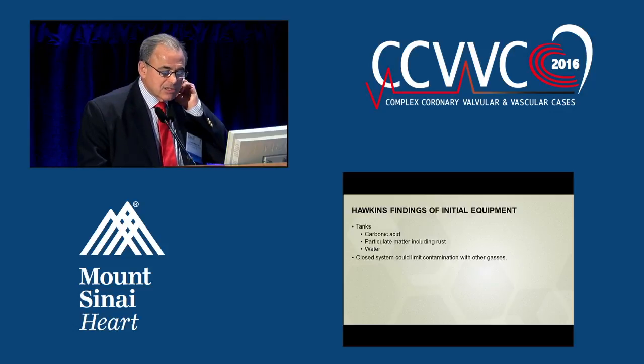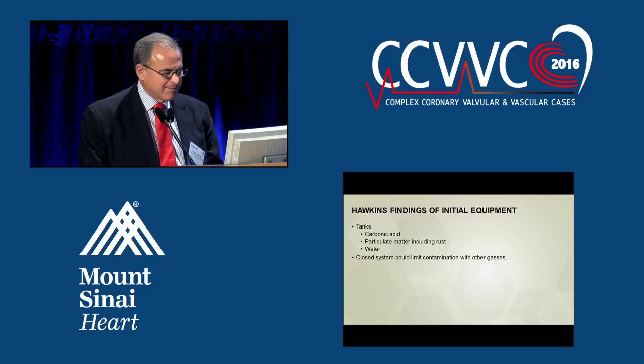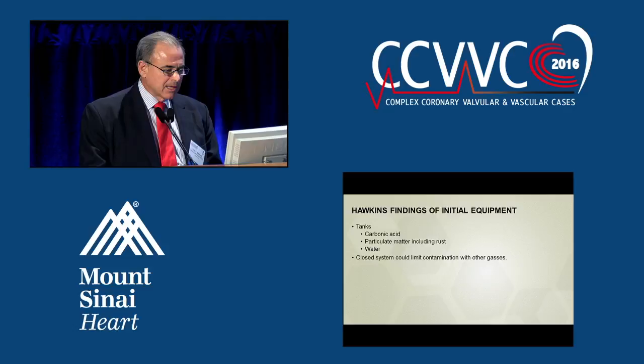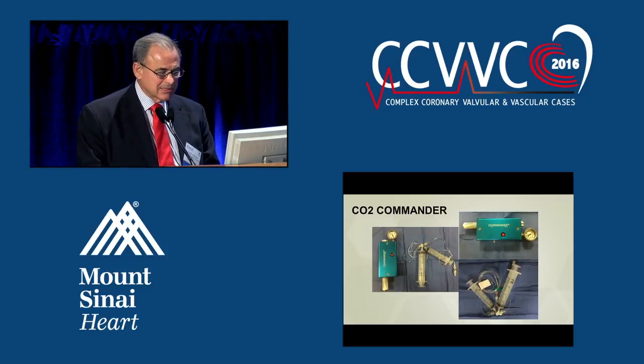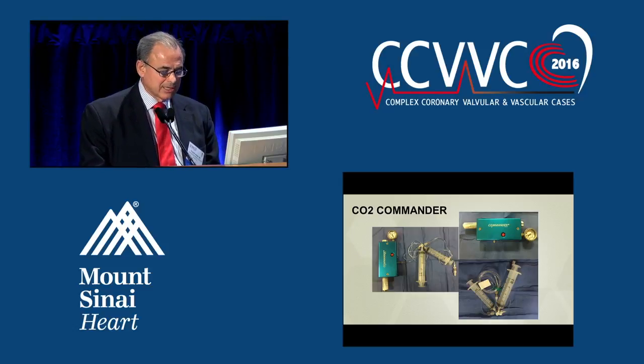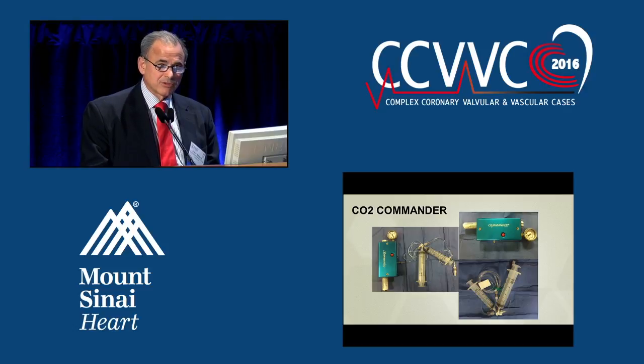Initially this was done using industrial CO2. When Hawkins looked inside the CO2 tanks being rolled into the cath lab, he found carbonic acid, particulate matter including rust, and water. He strongly advocated for a closed system. The system I currently use — small enough that the whole unit weighs under a pound — can be placed on the patient field and set up in under half a minute.